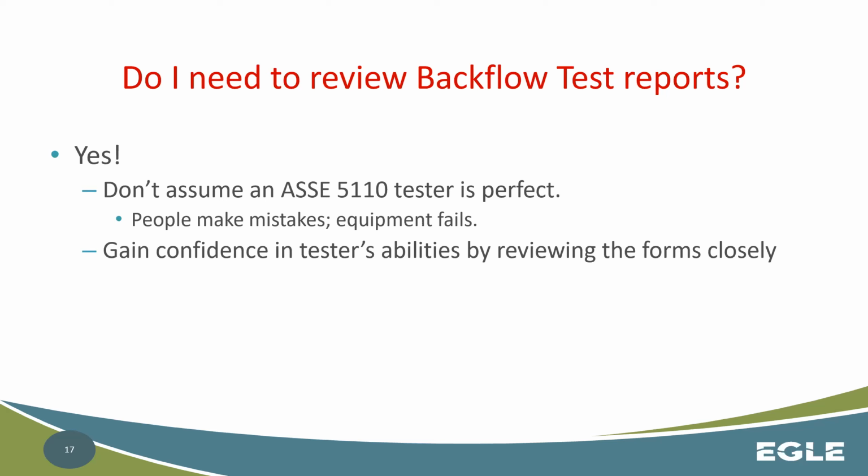You will know who's bad. And another thing you should do upon reviewing the records and maintaining them, you should go out and check that paperwork against the tag that is put on by that tester. If they're not putting a tag on, then you shouldn't use that tester anymore. Just take a word of advice.